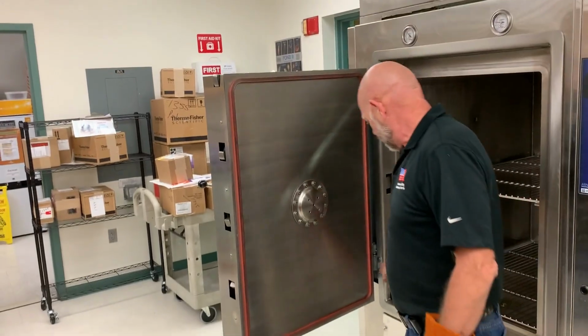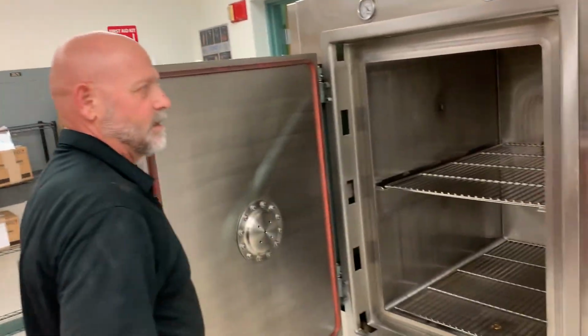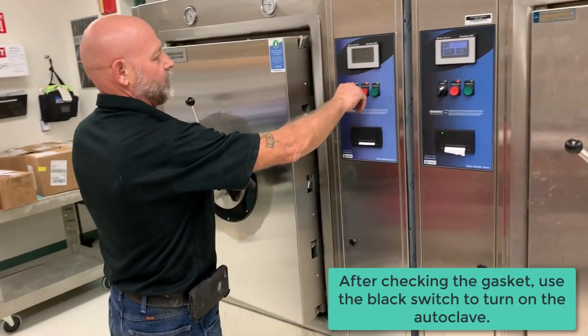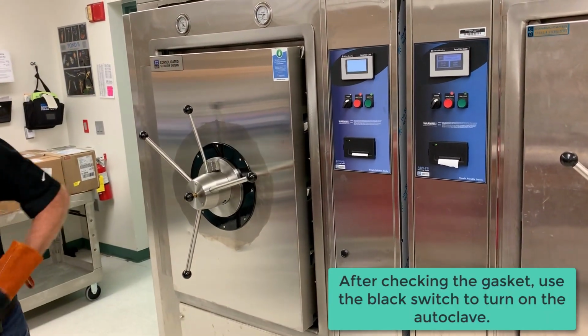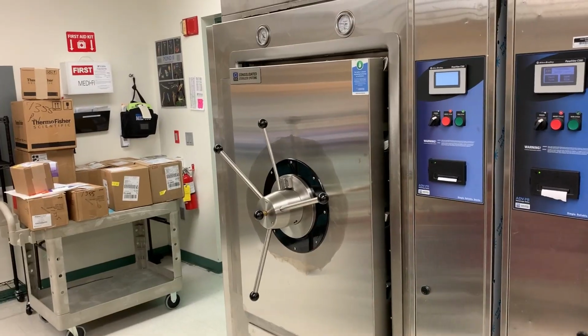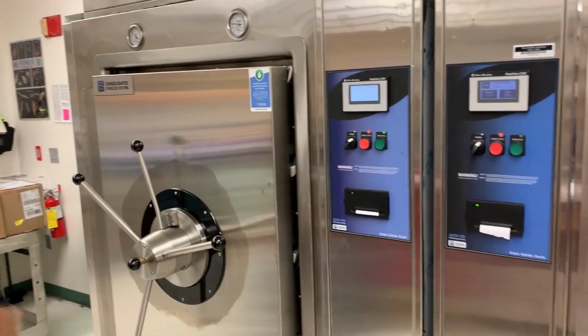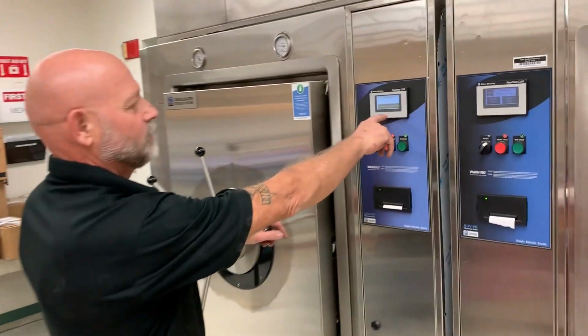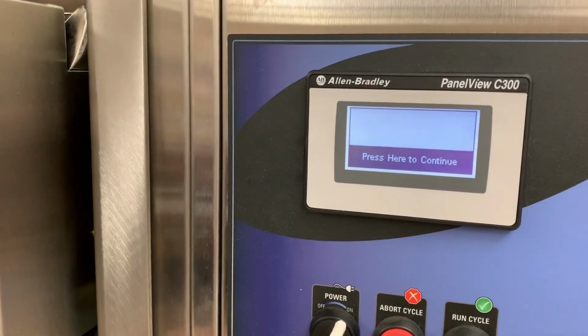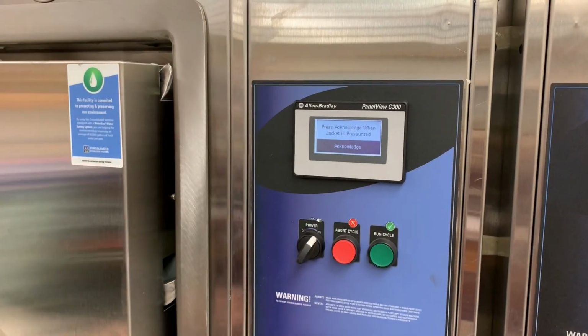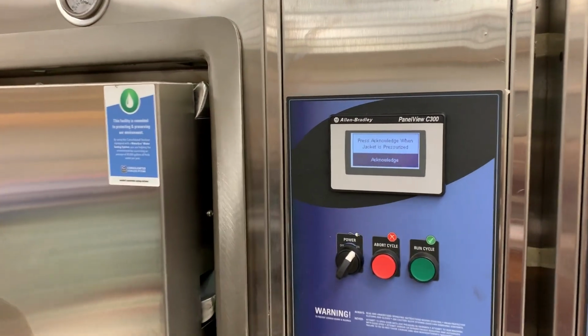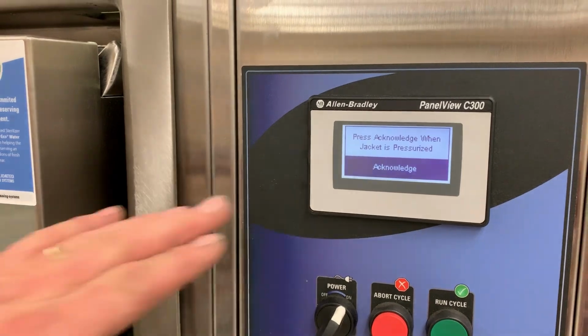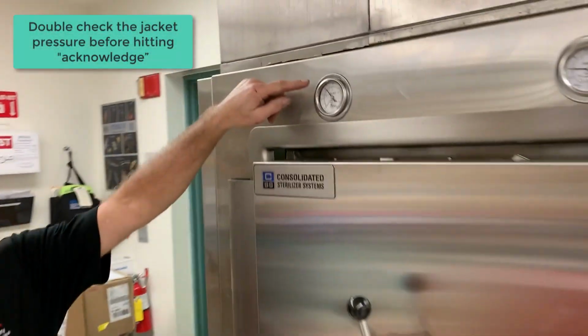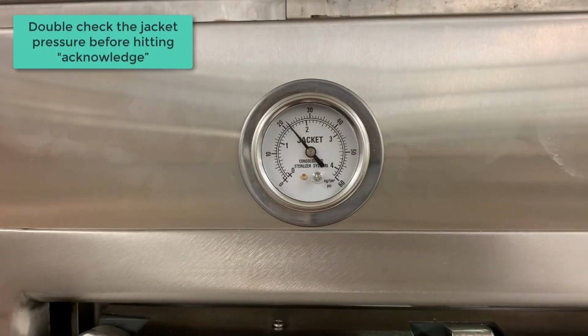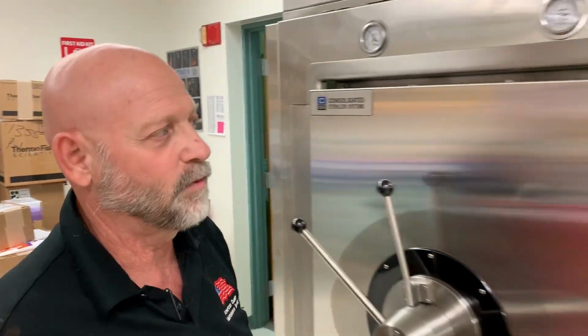Next thing you would do is inspect the gasket. Make sure everything looks good. And then you just turn on the machine. It takes about a minute to two minutes to load the programming. Okay, here you go. You can see what it's saying: there was a power interruption. Press here to continue. So now it's going to ask you this immediately. It wants you to acknowledge when the jacket pressure is up to 20, and you can't run anything until it is. So once the jacket pressure is up to 20, you hit acknowledge.